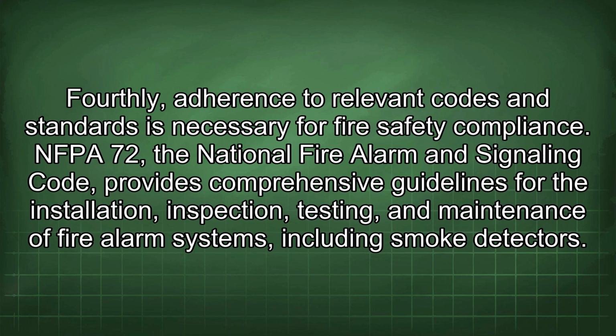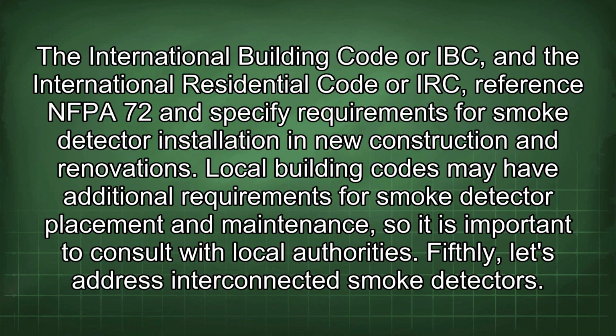Fourthly, adherence to relevant codes and standards is necessary for fire safety compliance. NFPA 72, the National Fire Alarm and Signaling Code, provides comprehensive guidelines for the installation, inspection, testing, and maintenance of fire alarm systems, including smoke detectors. The International Building Code, or IBC, and the International Residential Code, or IRC, reference NFPA 72 and specify requirements for smoke detector installation in new construction and renovations. Local building codes may have additional requirements for smoke detector placement and maintenance, so it is important to consult with local authorities.